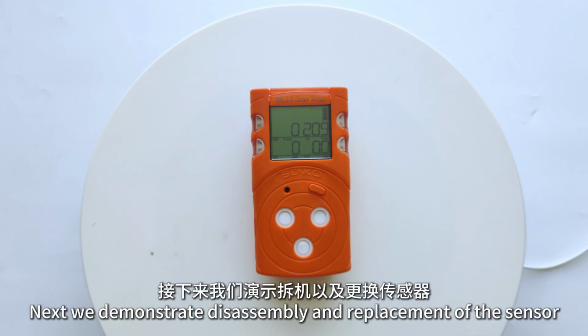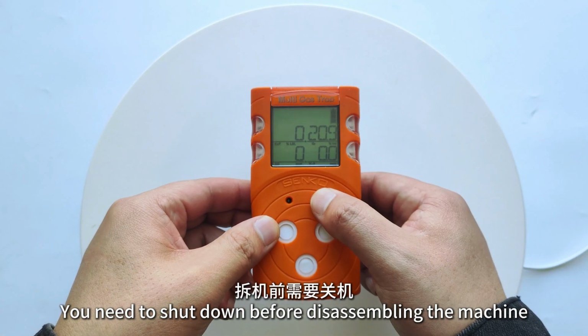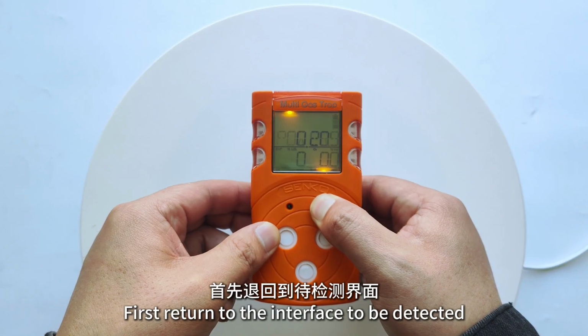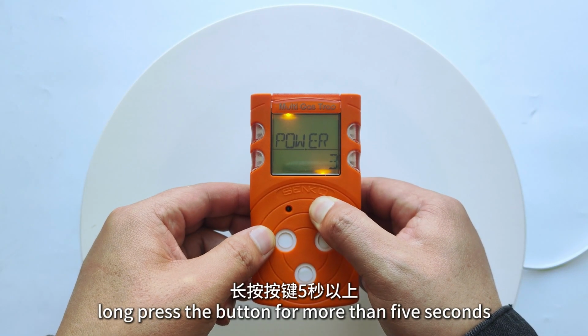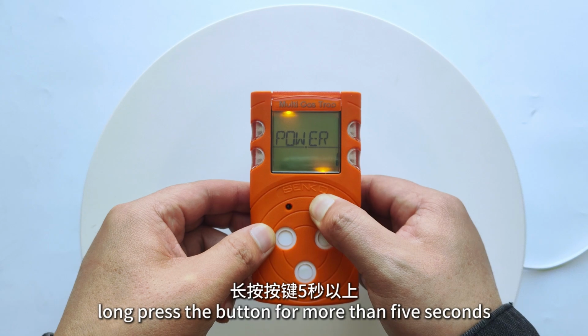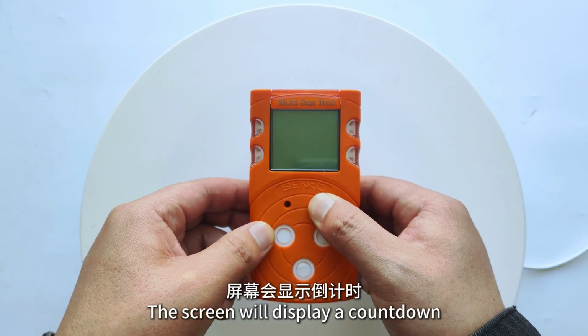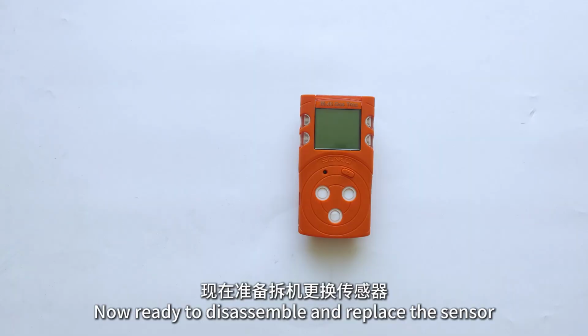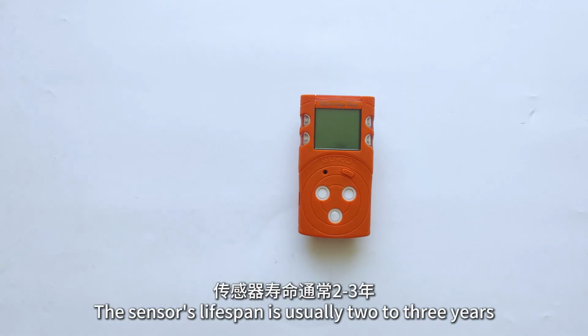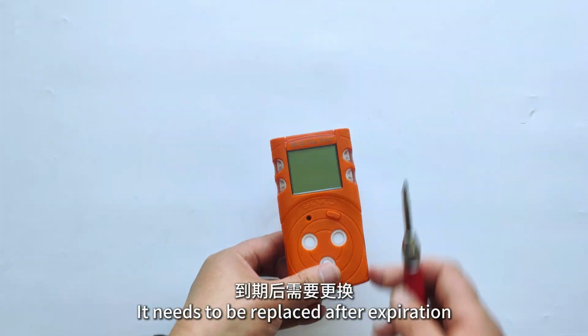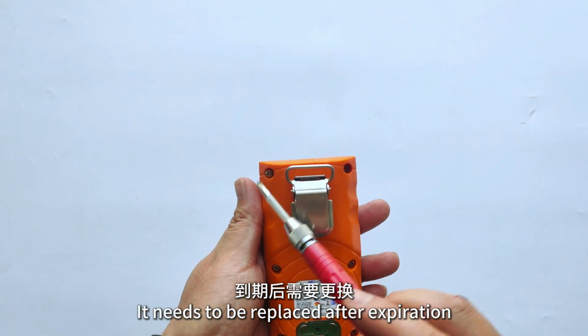Next, we demonstrate disassembly and replacement of the sensor. You need to shut down before disassembling the machine. First, return to the interface to be detected. Long press the button for more than 5 seconds. The screen will display a countdown. Then the device will be turned off. Now ready to disassemble and replace the sensor. The sensor's lifespan is usually 2 to 3 years. It needs to be replaced after expiration.